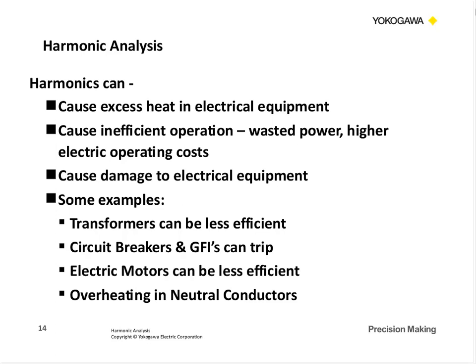Some examples might include transformers can be less efficient. Circuit breakers and GFIs can trip. Electric motors can be less efficient. We'll talk about that. We can actually, because of the harmonics, get some reverse torque on these motors, and so they're less efficient. And in the power quality area, overheating in the neutral conductors in places like our offices and things like that.